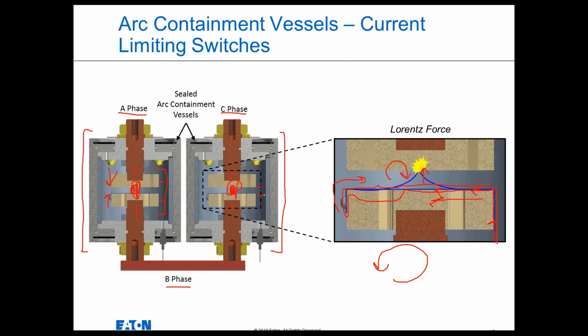Also, we know that arcing faults self-extinguish, believe it or not. If you create an arcing fault inside a piece of equipment and supply it with unlimited current and voltage for an unlimited period of time, that arcing fault will blow the equipment apart, and soon enough those contacts will melt far enough apart that the arc will self-extinguish. The equipment will be completely destroyed by then, but it will self-extinguish.